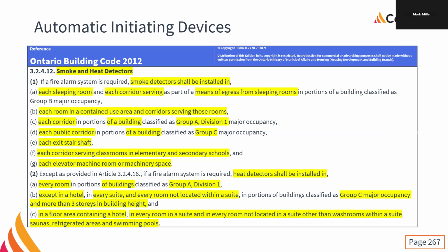And then each corridor in built portions of a building classified as Group A Division 1 major occupancy. Group A is assembly occupancies. Division 1 is assembly occupancies intended primarily for the viewing of the arts, like theaters and such like. So all the corridors get them there. Each public corridor and portions of a building classified as Group C major occupancy, our hotels, our apartments, our condominiums, the hallways get smoke detector.